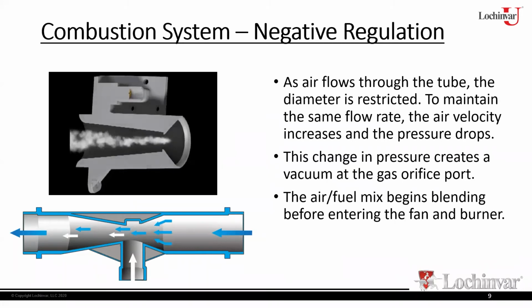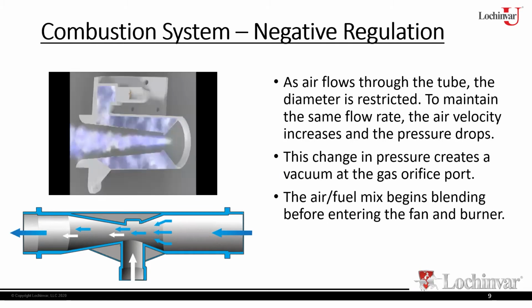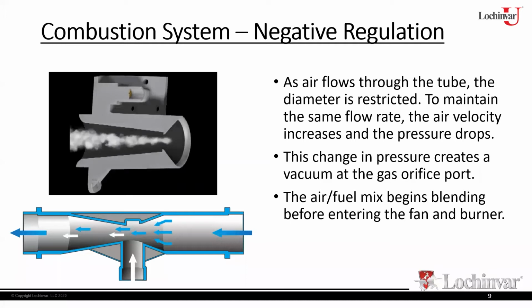So that means vent length, air intake length, blockages in either one of those, right? Dirty filters, dirty burner, dirty heat exchanger. Any of these things that obstruct our air movement through the system is going to affect our airflow. Now in some cases, that can be a good thing. If you have, say, a dirty burner and the burner starts getting dirty, it basically derates itself and protects the burner to a point. So sometimes that's a good thing. But again, it's all about airflow. If you're derating the heater, you're not getting max capacity out of it. You're not getting what you should be getting out of it. So we want to make sure everything is operating correctly and everything is doing what it's supposed to be doing. So airflow affects everything.